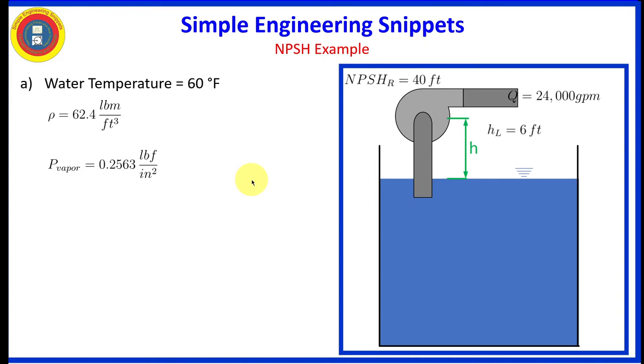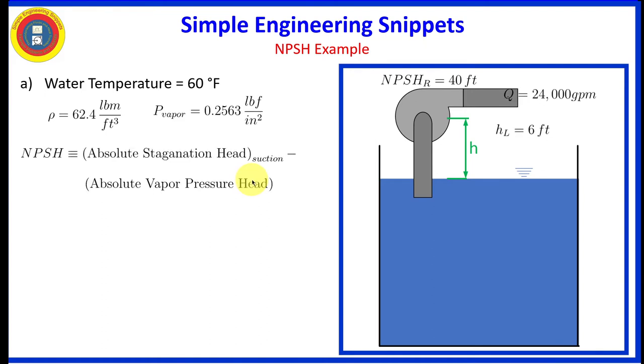Okay, so let's save some of our information. All right, let's review net positive suction head. Net positive suction head is equal to the absolute stagnation head at the pump suction minus the absolute vapor pressure head.